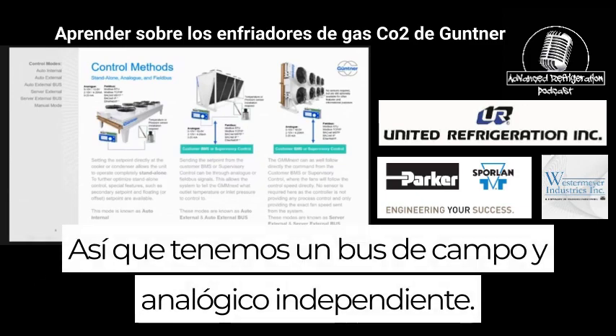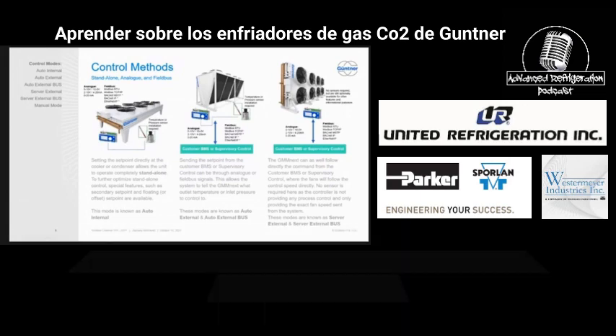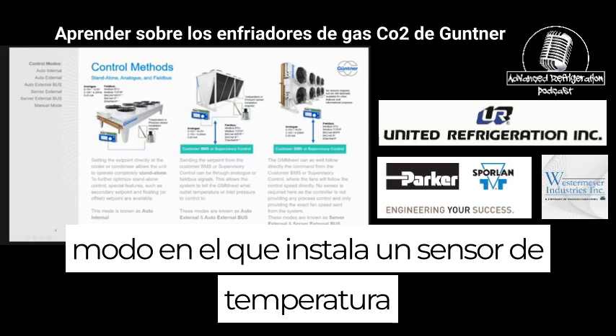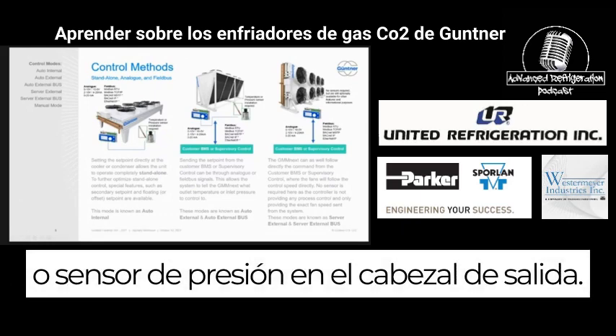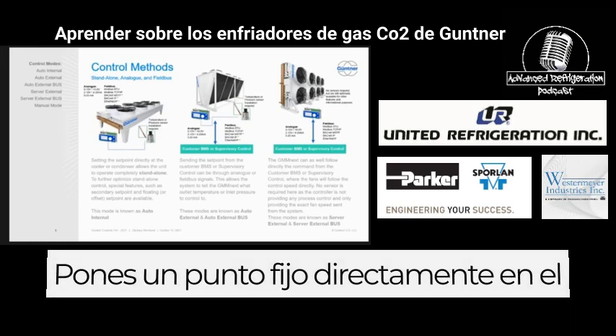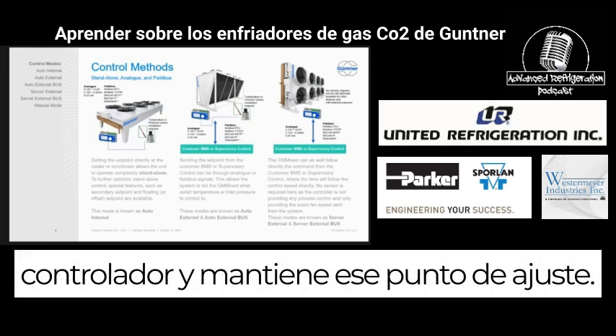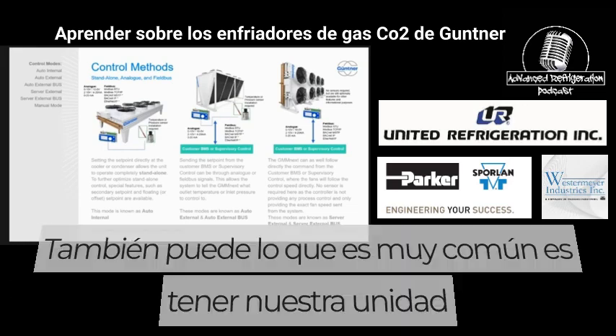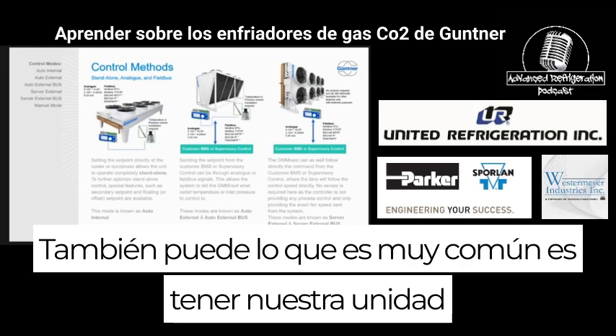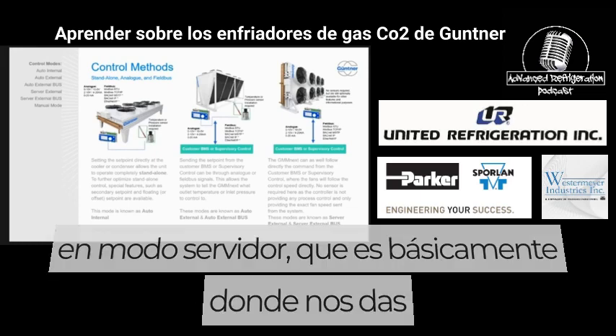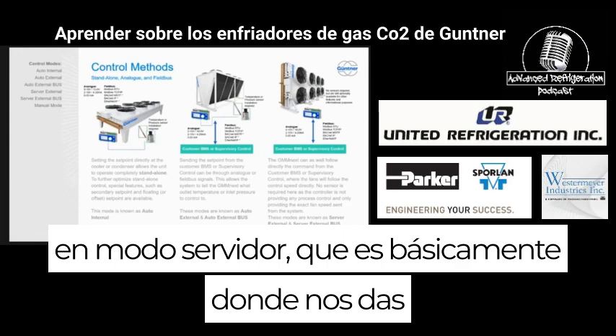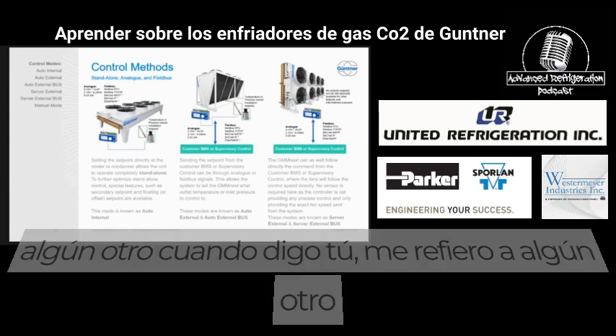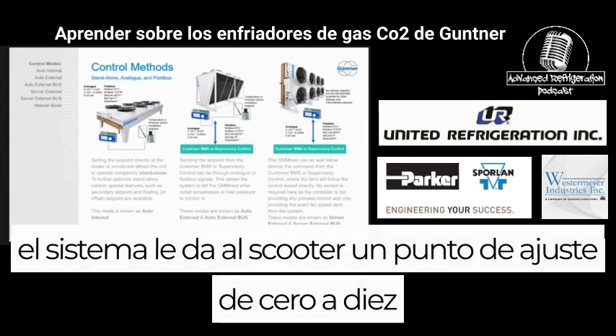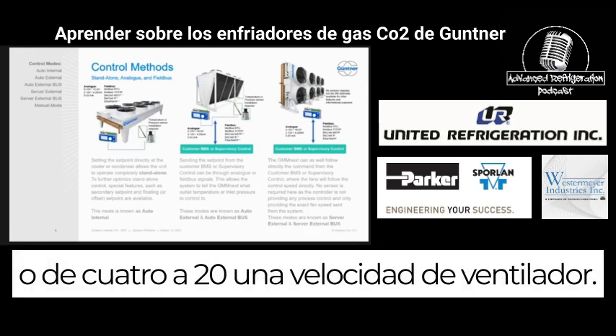So we have standalone, analog and field bus. The unit can be in standalone mode, where you install a temperature sensor or a pressure sensor on the outlet header, put a set point directly on the controller, and it maintains that set point. What's also very common is having our unit in server mode, which is where some other system gives Guntner a fan speed via 0 to 10 or 4 to 20.